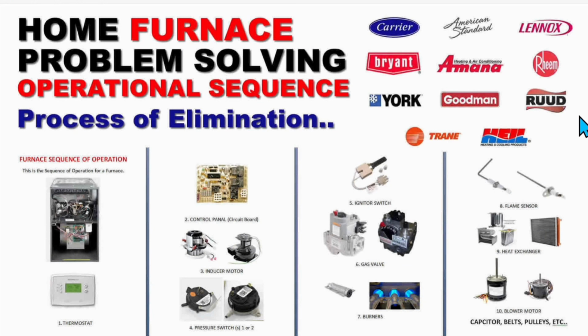Okay, we're upstairs. These are just a few of the different types of furnaces out there. I've owned a Carrier, a Lennox, a Rheem, and now a Goodman. This is the operational sequence for a basic furnace. And this is what that looks like. Control panel is going to be right there. The inducer motor is going to be up in there. You're going to have a pressure switch over here. Igniter switch is going to be there. Your flame sensor could be on the opposite side of your ignition switch on this side, but your manual will tell you where it's at.